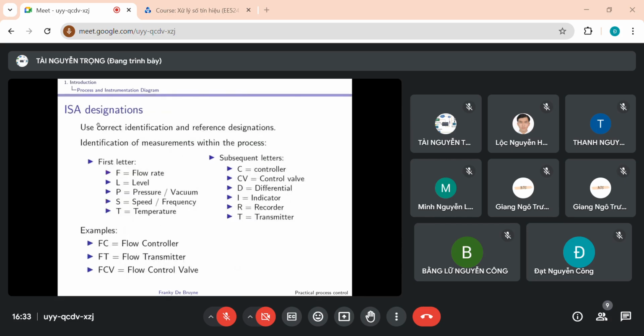Well, you should use the correct ISA identification and reference designations. Typically, for measurements within a process, the first letter relates to the type of measurement, so F for flow, L for level, P for pressure, and so on. The subsequent letters will have to do with the type of device. Is it a controller, a control valve, and so on. So here we have a few examples. FC stands for flow controller, FT for flow transmitter, FCV for flow control valve.